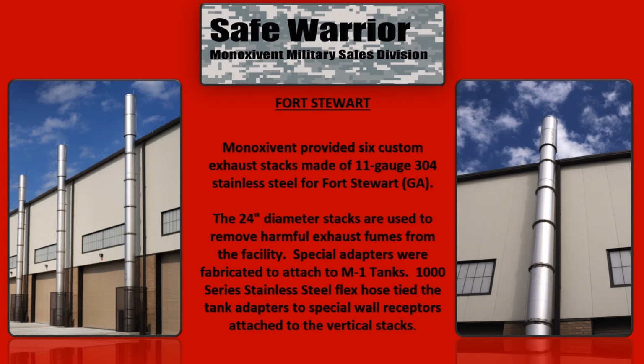And basically what we have here, and I'll show you a picture on the next page, is we've created a box that fits over the area where the exhaust comes out of the tank, and it's tied into some high temp hose, and then that hose is all tied into the foundation for these stacks. And then the stacks are on the outside, and the exhaust is captured through the tank. So each tank has its own bay. Each bay has its own capture system. The velocity is so strong that it's captured into the box through that vent system, into the hose. The hose then vents into the stacks, and the exhaust is evacuated through the stacks to the outside and dispersed. So the velocity is so strong in this particular application, there was no need for a fan. The velocity is so strong it forces its way through the hose to the stack, and from the stack then to the outside.